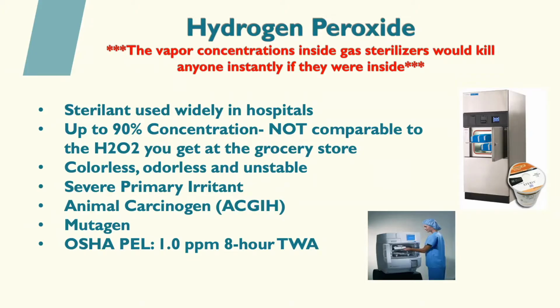Hydrogen peroxide is a strong oxidizer. It's more powerful than chlorine and chlorine dioxide. However, for disinfection, high concentrations are required, and that's exactly what's going on inside that sterilizer. When it comes in contact with flammable substances, it can spontaneously ignite. When it's mixed with organic matter, you may have a fire or an explosion. And when it comes in contact with certain metals, metalloids, or metal oxides, it could also result in a powerful explosion. This is why hydrogen peroxide is usually transported in diluted form and stored that way for safety. So again, I don't think something that has that potential can be considered non-harmful.